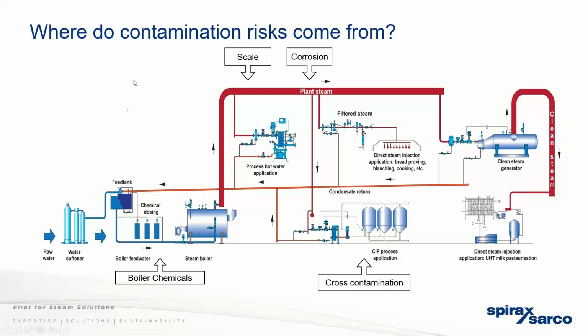So where do some of these contamination risks come from? Some of the risks are boiler chemicals, which I've talked about. In the pipework, there could be scale and corrosion, and also cross-contamination. So processes like CIP, or production processes where you have a steam heat exchanger. The condensate returning back to the feed tank and continuing on to the boiler could have some contamination in it that could transfer into your process. So there are contamination monitoring systems that you can install in condensate just to dump any contaminated condensate when it comes through.